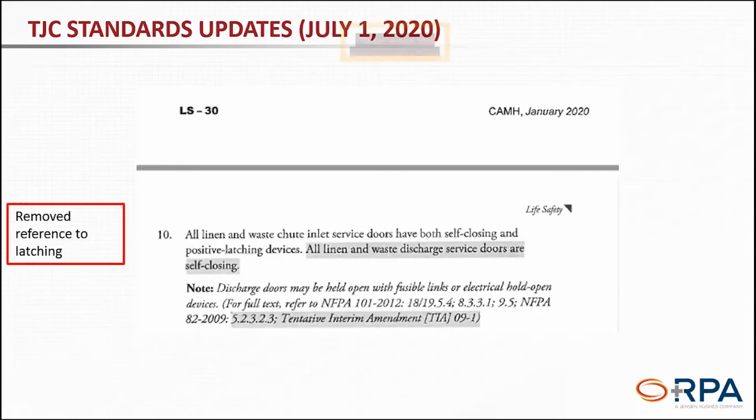So for a long time CMS and the Joint Commission would require that door to latch, positively latch. Well, the later editions of NFPA 82, which is the chute standard, they removed that requirement for the latching in some cases because of the angle at which the guillotine slides, etc. So that is one important note, that they removed that reference to latching. That was a big deal, and allowed people to keep the doors that they've had for a long time.